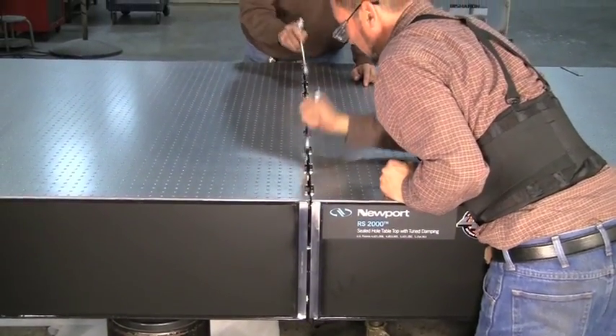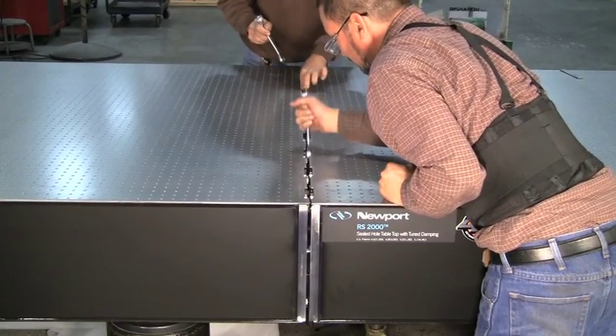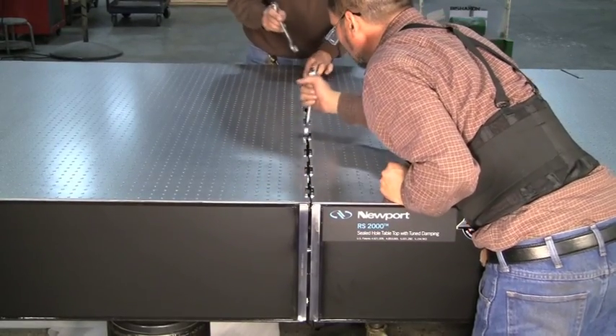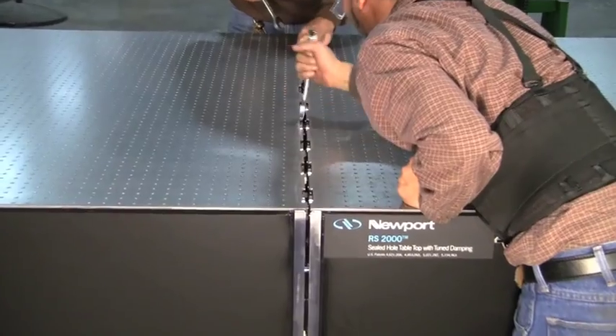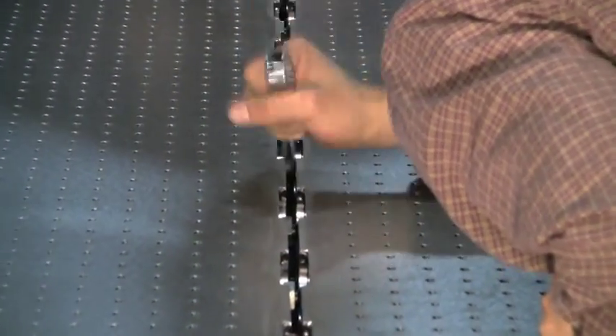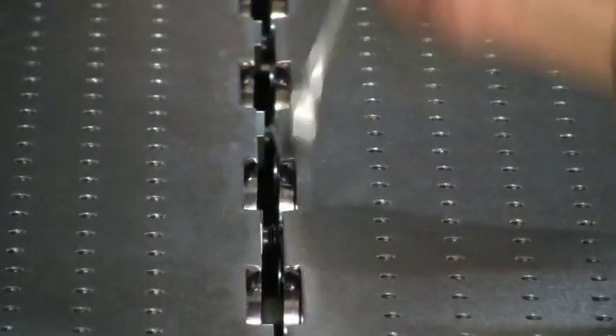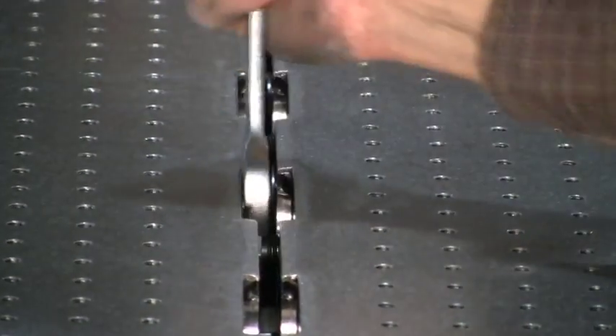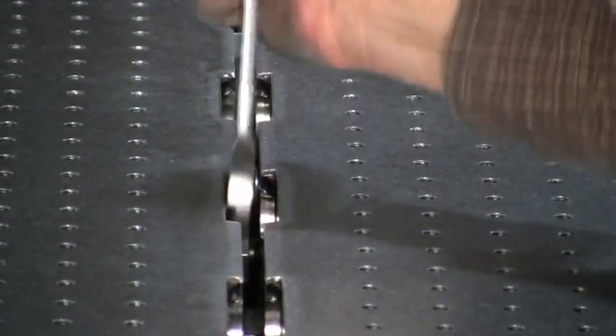Continue hand-tightening the bolts until the two faces come in contact with each other. Continually inspect the gap between the table sections to verify uniform closure. Also be certain that the bolt heads remain centered between the table sections. If any bolt heads are touching either doubler plate, it may cause binding or misalignment.